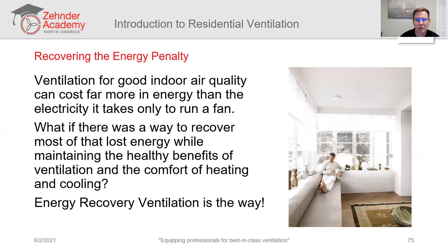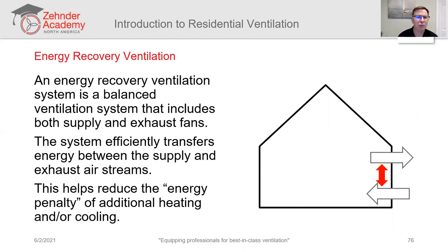And so if we can do some energy recovery on the ventilation, that's a really smart thing to do. We want the comfort of ventilation all year round. We want the benefit of ventilation all year round, but we don't want it to be uncomfortable, and we don't want it to cost us a fortune in operating costs. So energy recovery ventilation is the way to go. Energy recovery ventilation is employed on a balanced mechanical ventilation system where you have both supply and exhaust fans. You are both pulling outdoor air in and pushing indoor air out. And energy recovery is being accomplished between those two air streams.